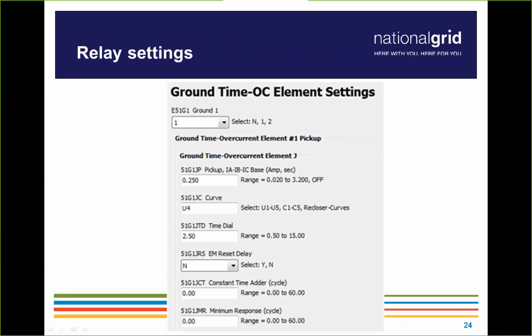If it was settings for some kind of a breaker and the settings were dial settings or some other kind of program setting where you would interface with a graphic interface on the breaker itself, we would require you to submit a list of those settings in order for us to do a proper coordination review with our upstream devices. As far as inverter settings go, those, again, are going to be treated similar to that graphic interface on a breaker, where we would require you to submit what those settings would be programmed to be in the inverter, on some kind of a list or the drawings, some format where we can look at them and say, yes, we agree with the settings for the over and under voltage and over and under frequency settings, and we can go ahead and move forward with the project.